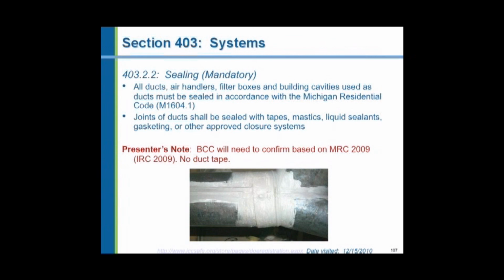This photograph is an example of a mastic sealant applied to duct. It's not pretty, but it works well, and I recommend this. It seals tightly, hardens, glues the ductwork together. It's also possible to use tape to seal joints and seams in ductwork. The duct tape that we commonly purchase at the hardware store, the cloth duct tape, silver in color with an adhesive backing, you know from experience, will fall off of a surface. After a period of a year or two, this adhesive will cure and the tape will fall away. It is not a permanent seal for ductwork.